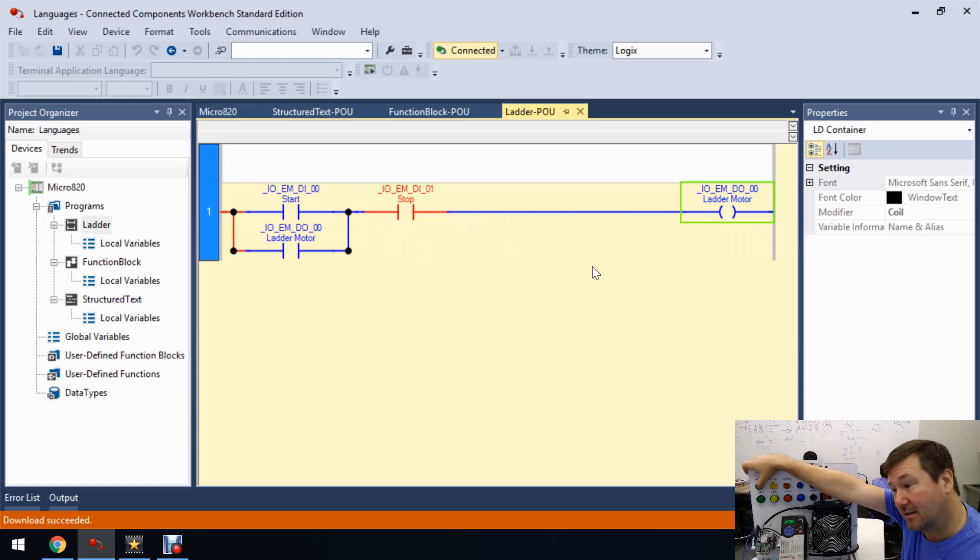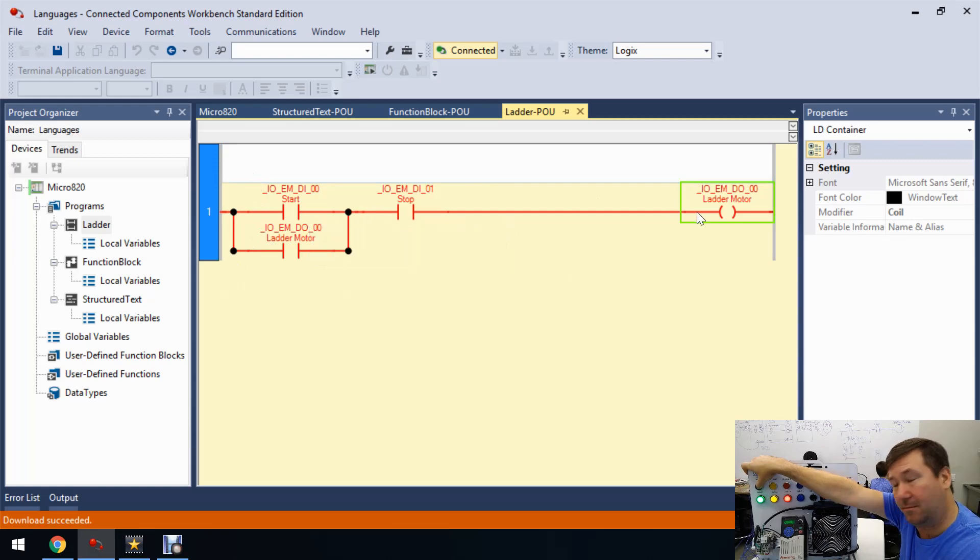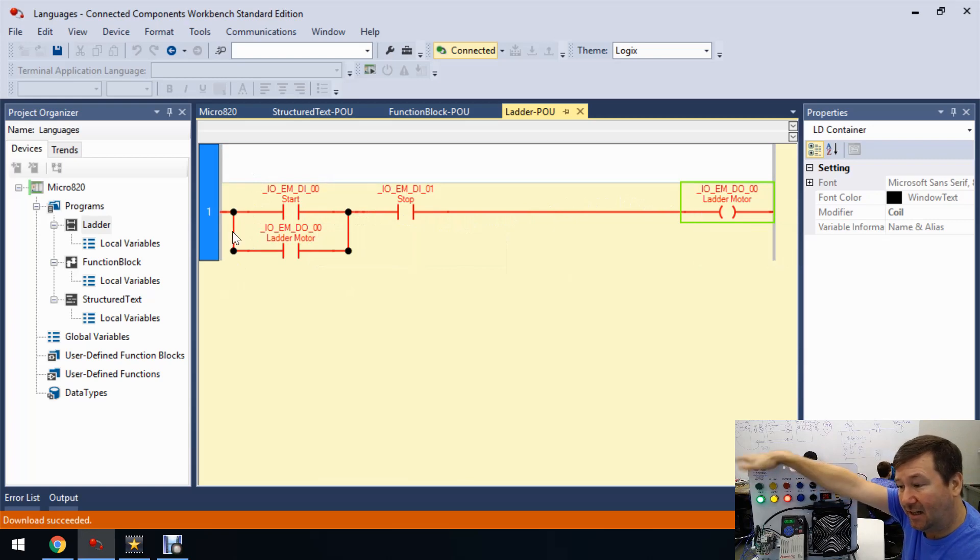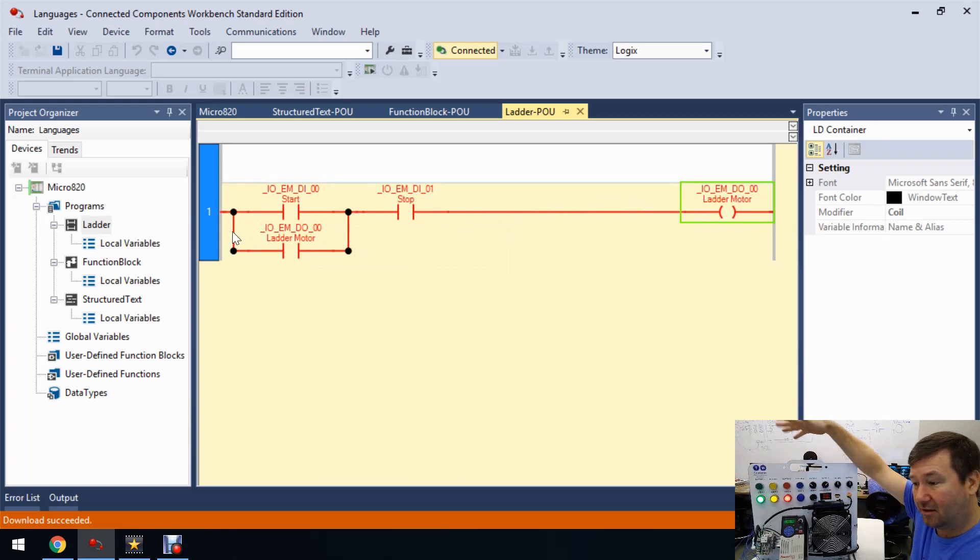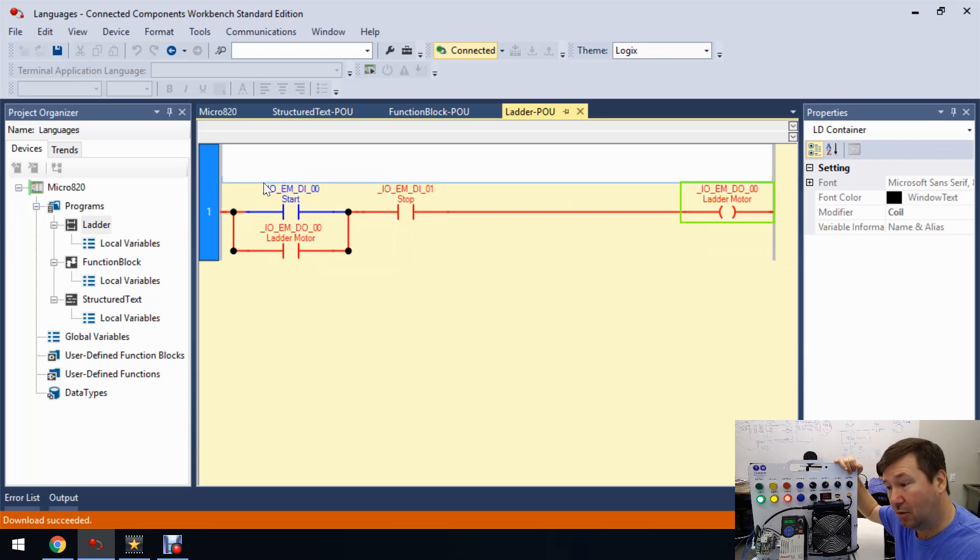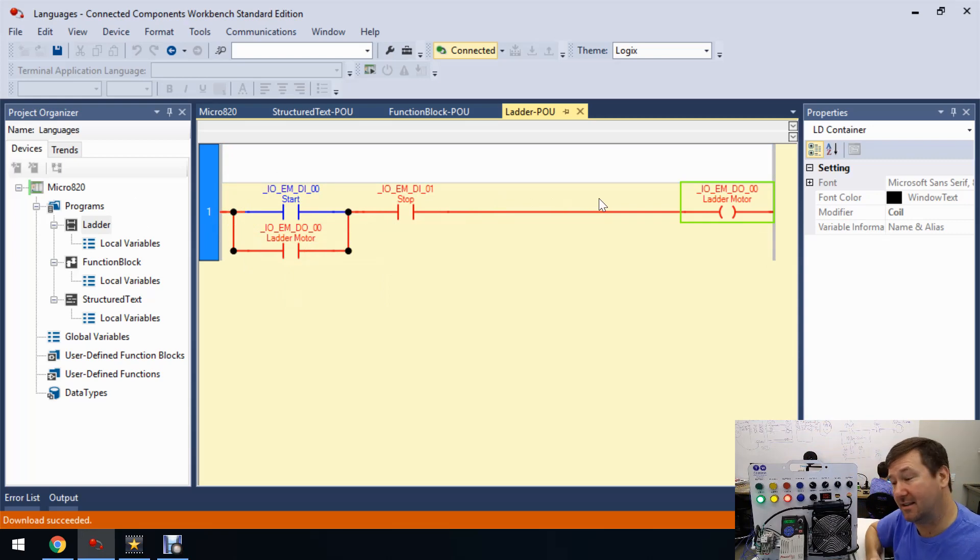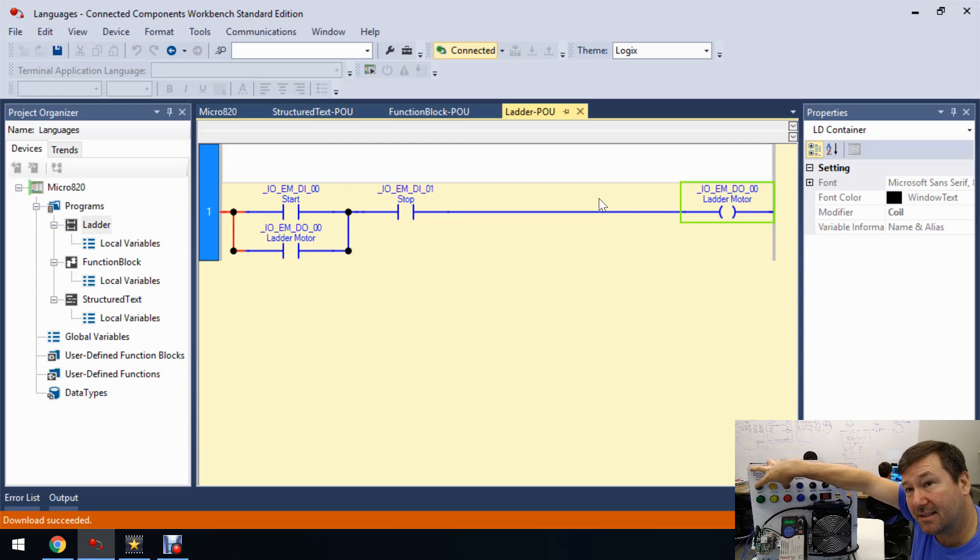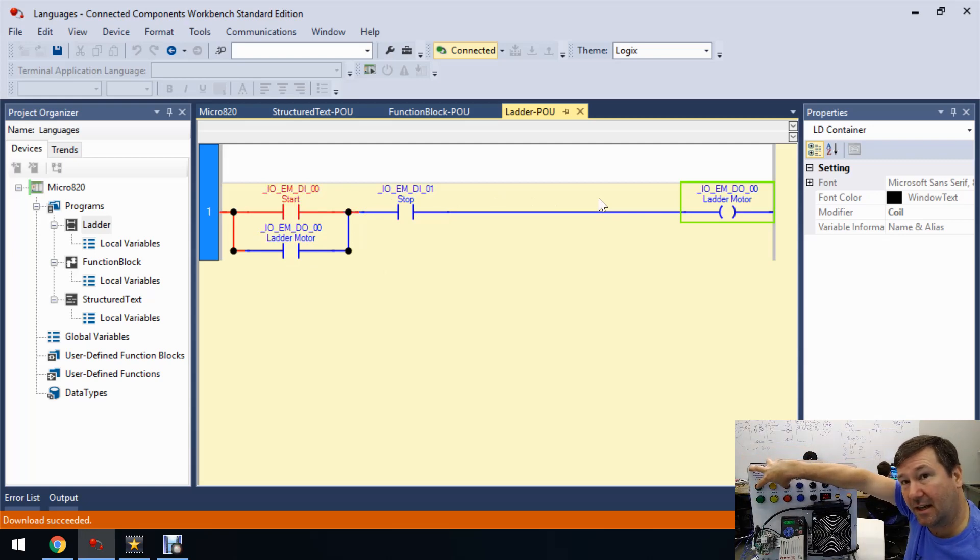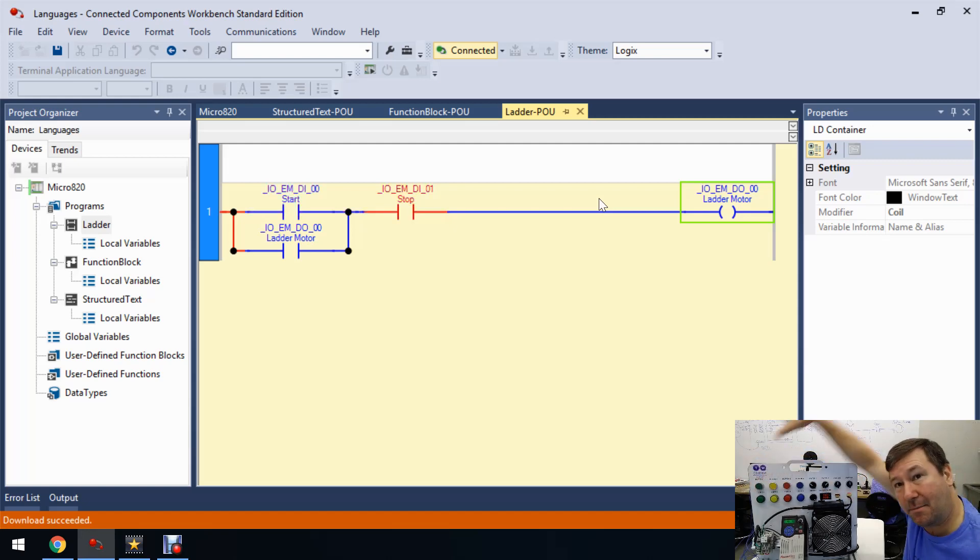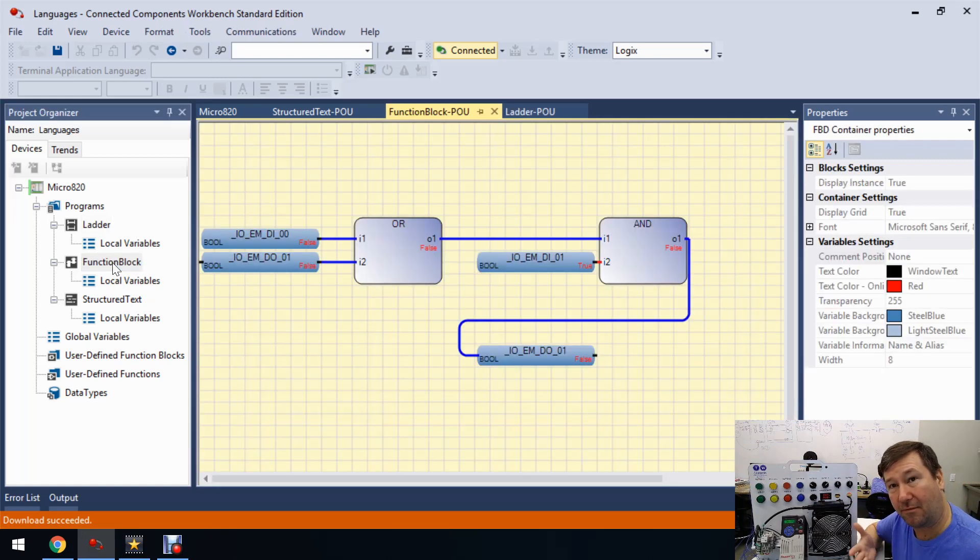So if I press the start button, then yes, our start is now true. We have a continuous path from left to right. Our motor comes on. And when we let off of the start button, then we can see that it is now blue, which means it's not true. But we're getting a continuous path of trues from left to right through that sealing now. So pretty obvious for troubleshooting, whether it be that the stop button is stuck. And so we're pressing the start button and it won't come on. Or if we press the start button and nothing's happening, pretty easy to troubleshoot.